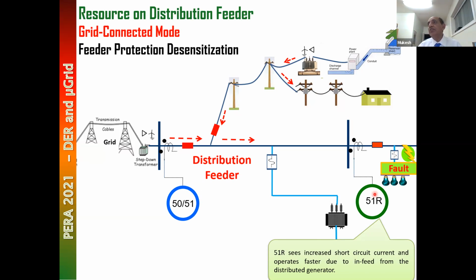Now, when I'm saying the short circuit current level is increased, first you have to check that this circuit breaker or this recloser can withstand this increased short circuit level. If not, you have to replace it and put in a higher rating circuit breaker. So the first point is, short circuit current here is increased. You have to make sure this recloser or this circuit breaker has the capability to handle the increased short circuit level. If not, you need to replace it. So that's the first change you have to make, or not make if it is within that capability. Now, on the protection basis, it is good, but on the recloser, the circuit breaker basis, you have to make sure that it has an interrupting capability.